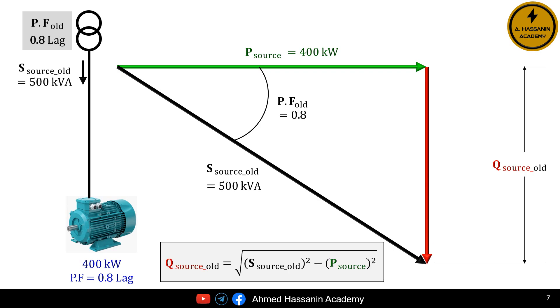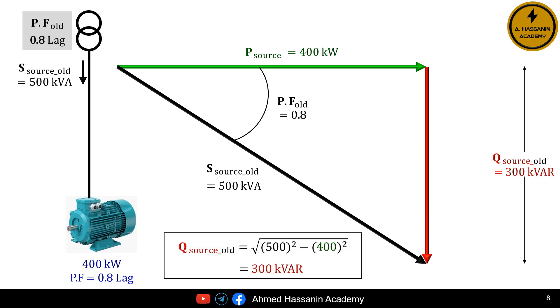So we can calculate the reactive power of the source before installing the capacitor, that is, before improving the power factor. Q source old is equal to the square root of (S source old)² minus (P source)², which equals the square root of (500 kVA)² minus (400 kW)², which equals 300 kilovars.